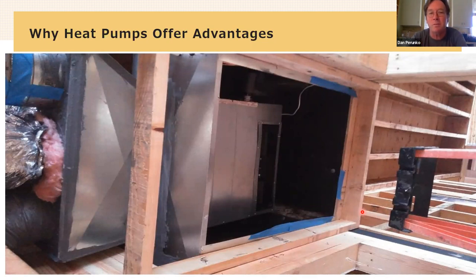And so the weird thing you're looking at here is, and it's super hard to get a photo of this. So the angle is funky because it's so hard to photograph. This is a giant metal plenum, and it's the return side of the system, the side that's sucking air in. This is the opening in the air handler where the air enters, the return opening. This is the air handler itself.